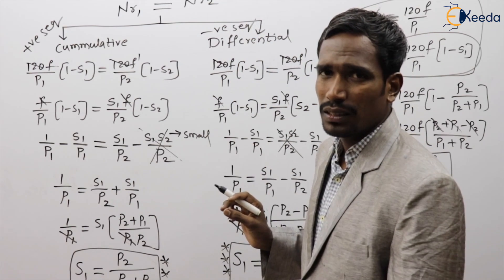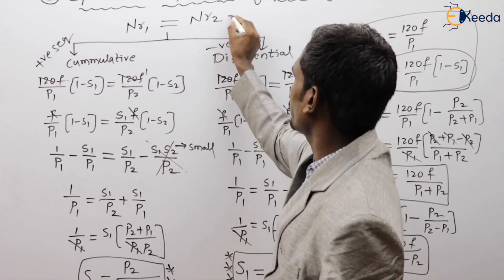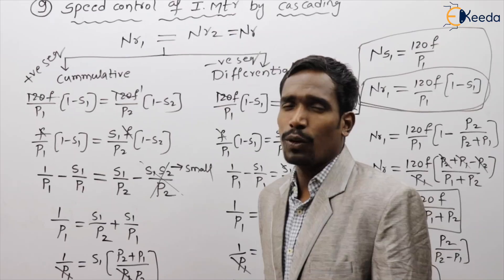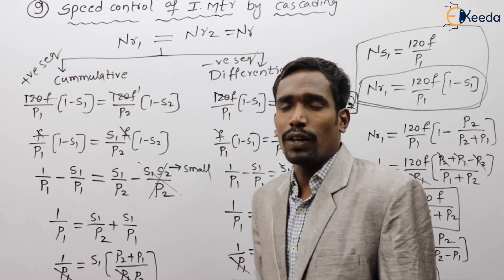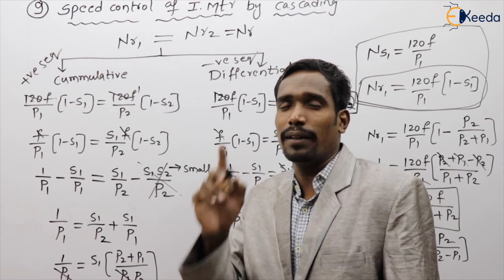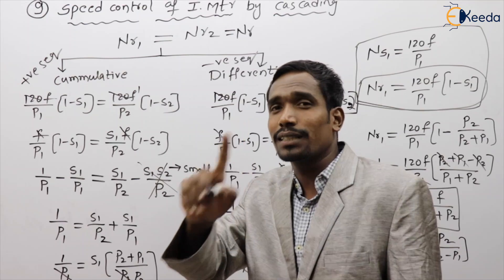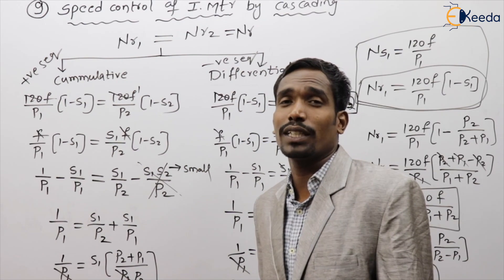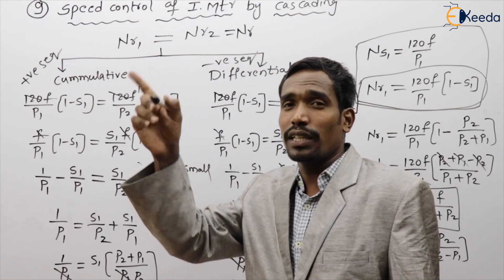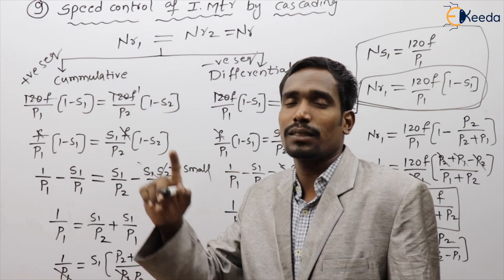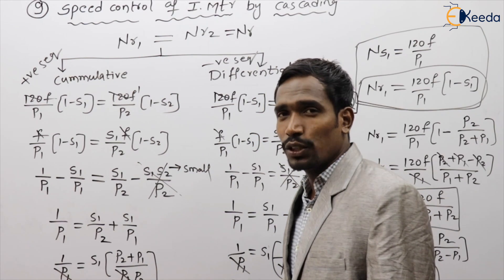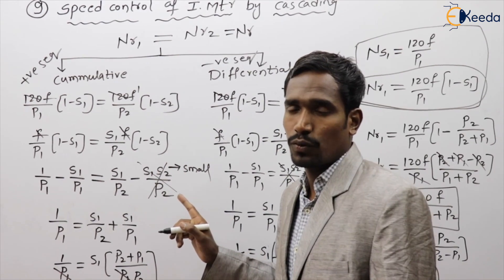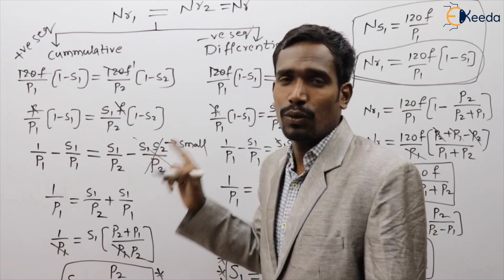In summary for cascading: nr1 = nr2 = nr. For cumulative connection, the rotor speed is 120F / (P1 + P2). For differential connection, the rotor speed is 120F / (P1 − P2). The slip values follow accordingly from these results.